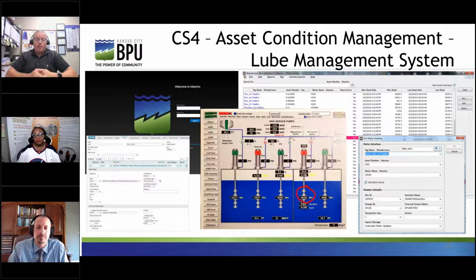If high in particle counts, we filter the oil with filter carts and resample. If high in iron, we generate an ad hoc vibration ultrasound work order to see if there's a change from previous quarterly readings. If viscosity has changed significantly, we'll either sweeten or change. Doing work this way gives us a good idea what's going on with our motors and helps us better maintain them for a longer life versus the old ways.